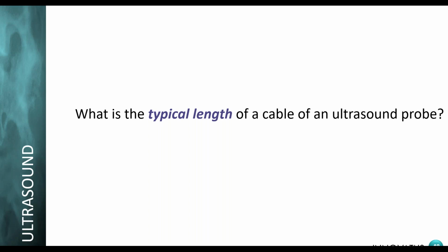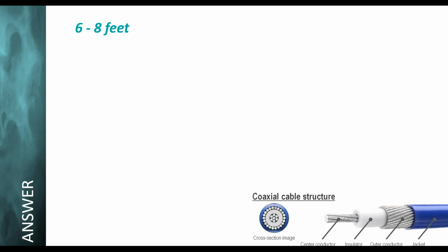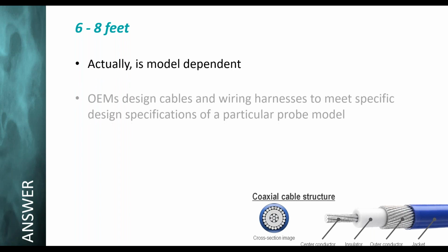That's a good answer, but be more specific. 7 feet is about average, but it's really 6 to 8 feet, and it varies. With a standard abdominal or vascular probe, you're looking at about 6 feet. Cardiac probes go up to 8 feet because of the cable routing needed for the echosonographer to do the exam. Endovaginal and endorectal probes are usually 9 to 10 feet for a more circuitous route, for patient comfort and exam ergonomics. So the average is 6 to 8 feet, but it is model dependent.